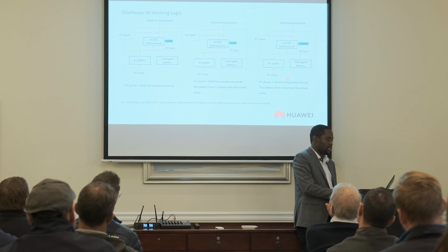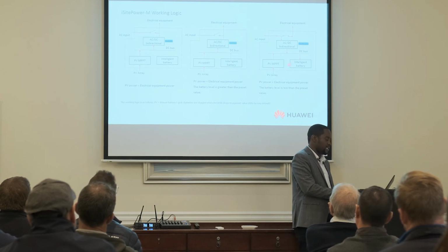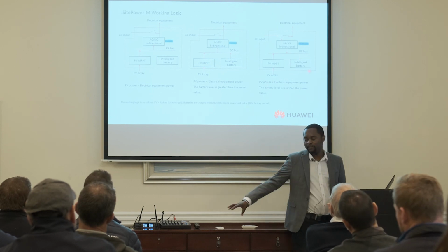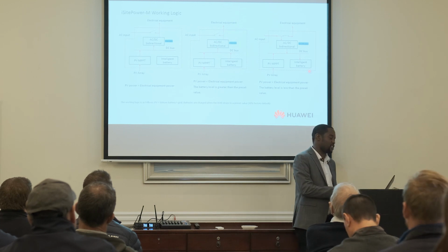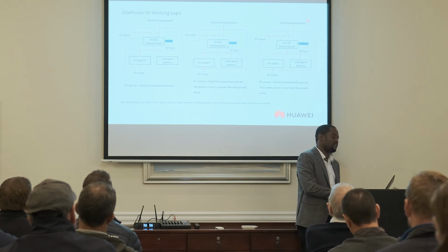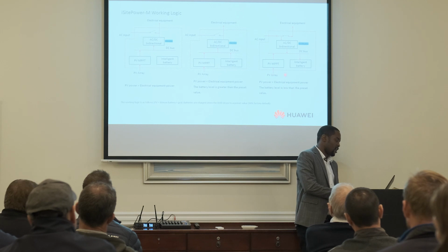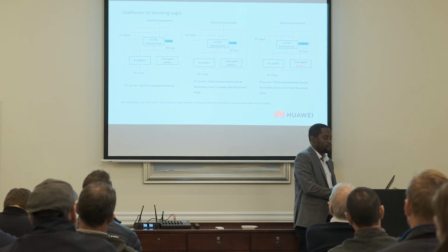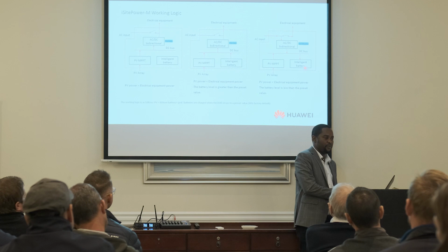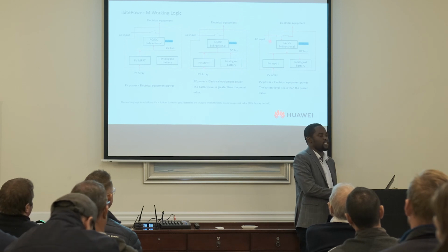The other scenario is, let's say your PV is not enough, right? Then you are discharging the batteries at 2.5, the 0.5C. Still, it's not enough. Your loads are demanding 5 kilowatts. You are producing 2 kilowatts from your strings. Then the battery can give you 2.5. Then you are now at 4.5. Then the other 500 watts you can take from grid.